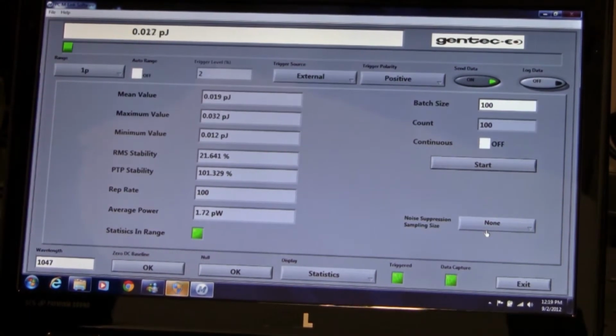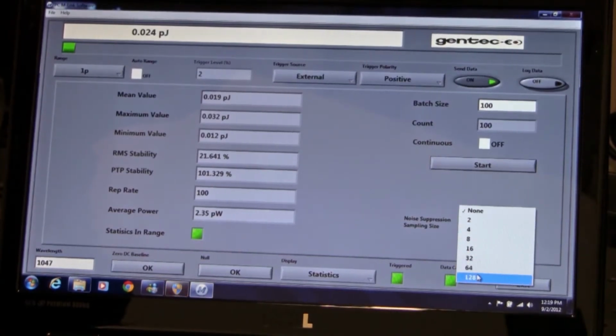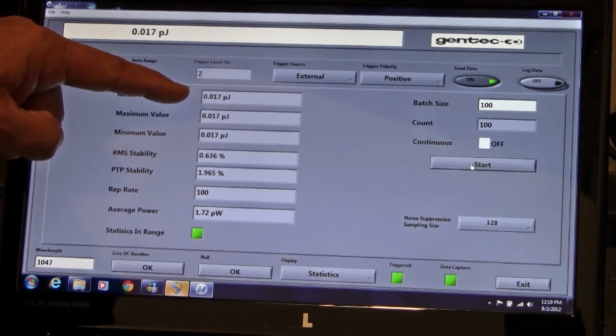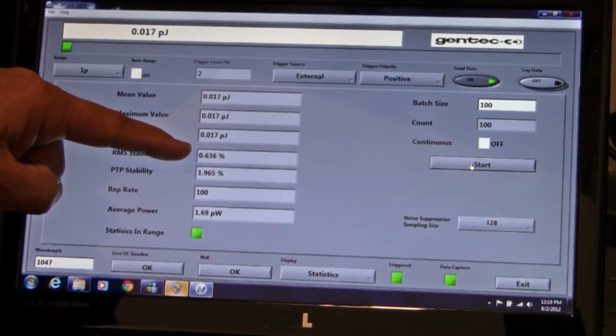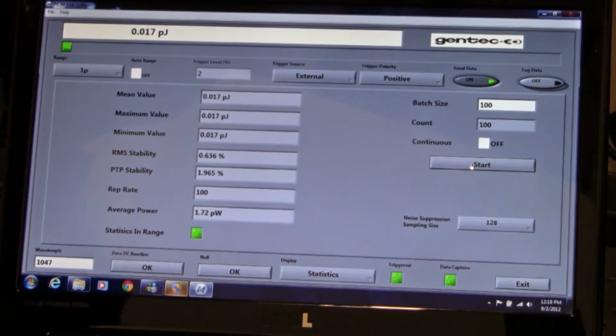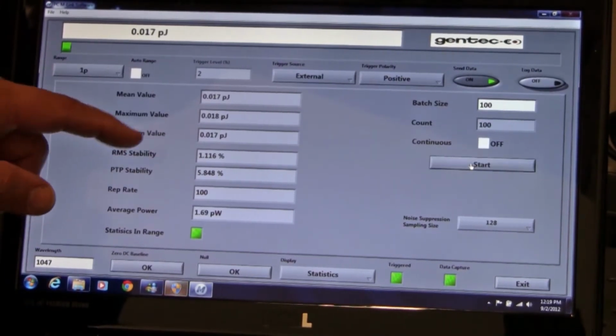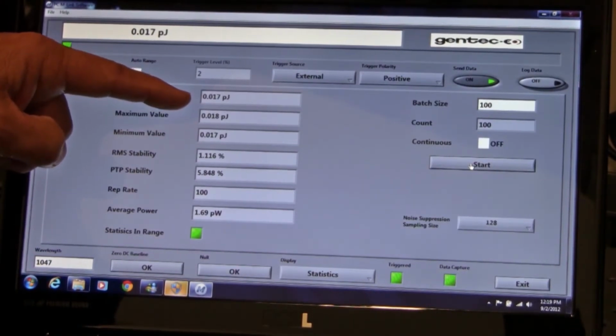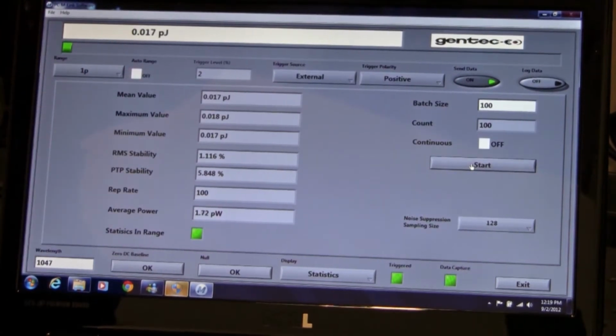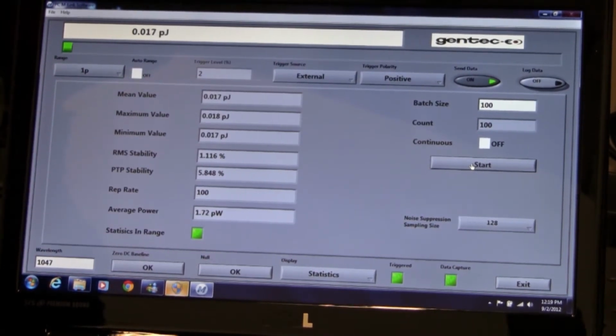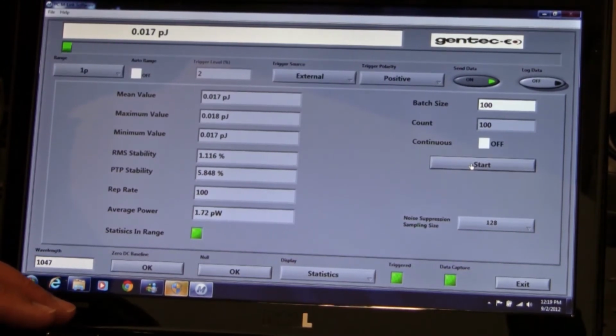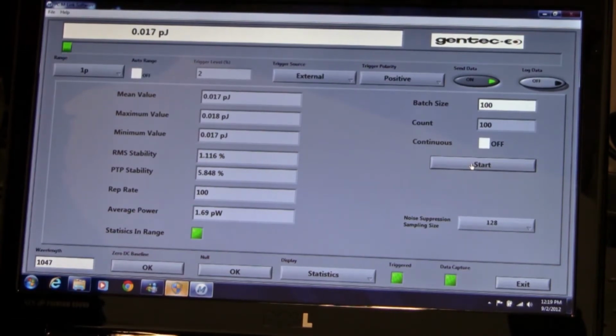So now we'll take advantage of the unique noise suppression feature of the software. I'm picking 128 pulses. I'm going to take a data set, and you'll see now we're reading 17 femtojoules with 0.636 RMS stability. If we take another data set, you'll see something very similar, 17 femtojoules and about 1% RMS stability. This can only be achieved at this energy level using external trigger and this unique noise suppression feature.